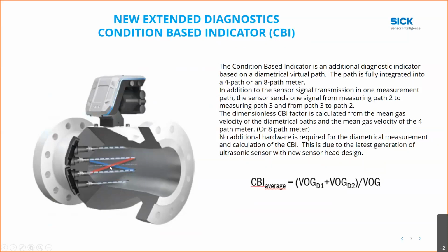Now, as everyone that has these meters out in the field knows, if you have a 4+1 ultrasonic meter, you can do some things with the 1-path compared to the 4-path. So this particular 4-path meter that we're seeing here can give you some of the same diagnostics that that 4+1 meter gave you in the past.